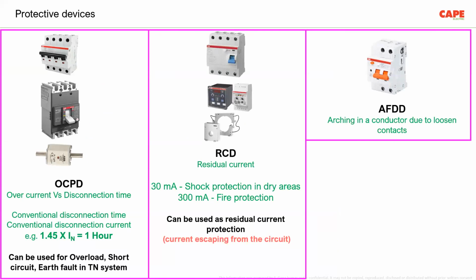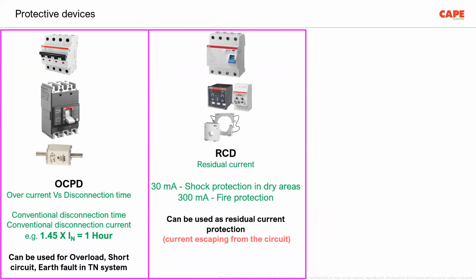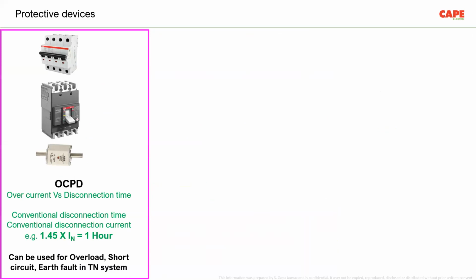All of you know that in an electrical installation, you need different protective devices. The first one is OCPD, overcurrent protective device, nothing but our fuses, MCBs, MCCBs. The name calls OCPD, overcurrent protective device. It means whenever there is a current more than its capacity, this device is supposed to trip. So with this name, a lot of engineers believe that if you use a 10 amps MCB and if the current is 11 amperes, it trips. Or if the current is 12 ampere, 13 ampere, it trips. Of course, sometimes it trips, but it takes a lot of time. So not only the disconnection current, but disconnection time is also equally important.